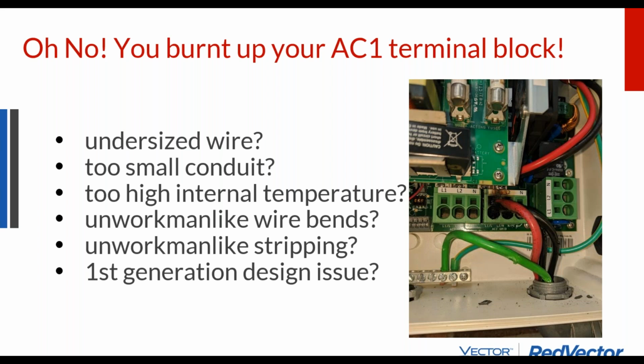So anyway, let's diagnose this problem up on screen and try to determine if it's an arc fault or a ground fault, because that'll help us figure out what went on here. So here we have the inside of an inverter block, and we've got leg 1, leg 2, and neutral. So this is going to be on, and we can see down here it says AC grid. So this is the grid side coming in from the grid. So it's probably not a DC side solar array issue. And so, obviously we've got some heat going on here.